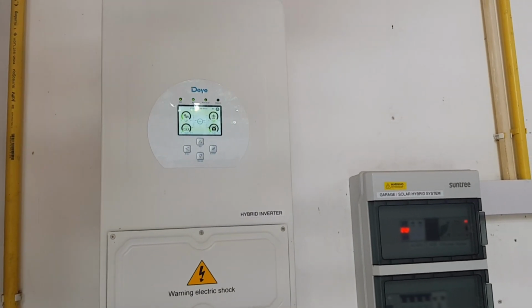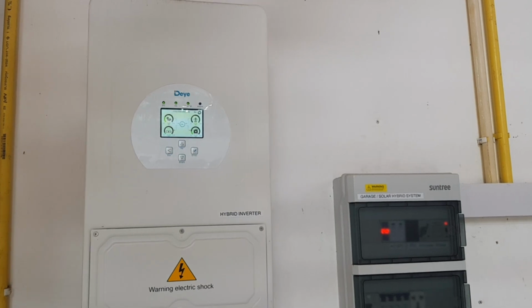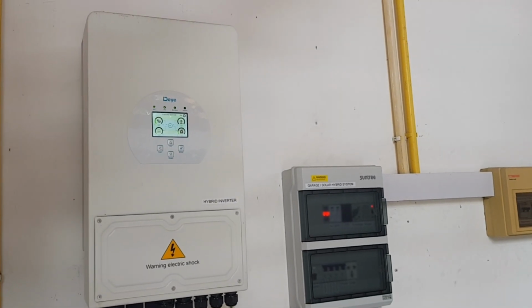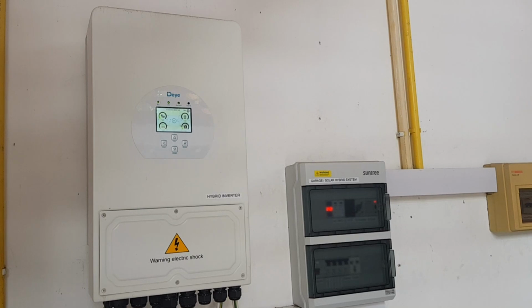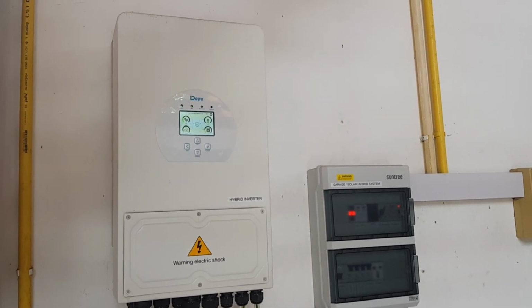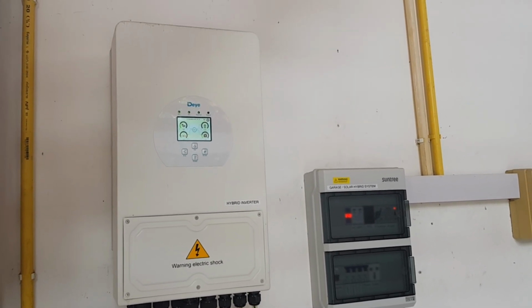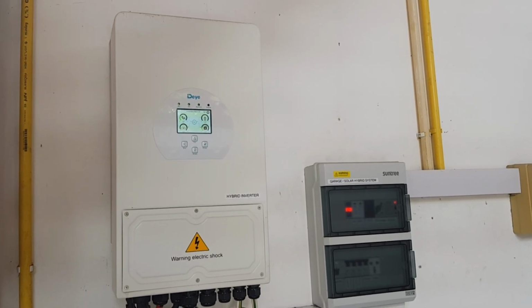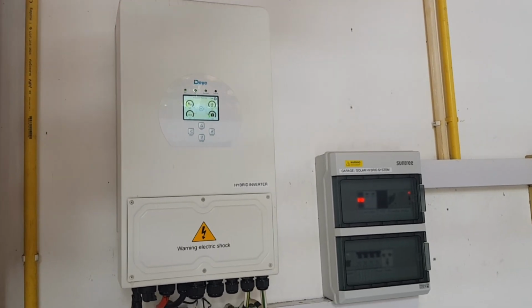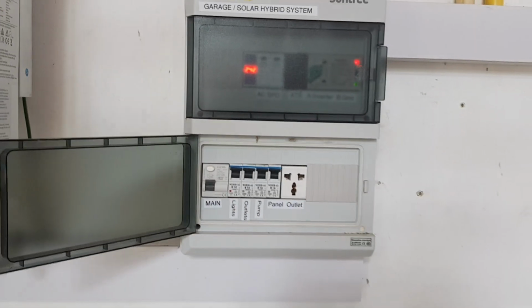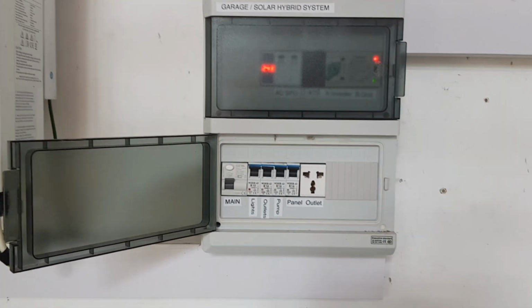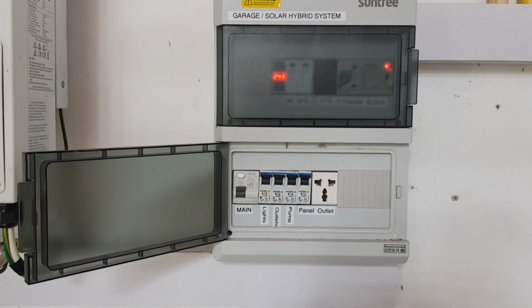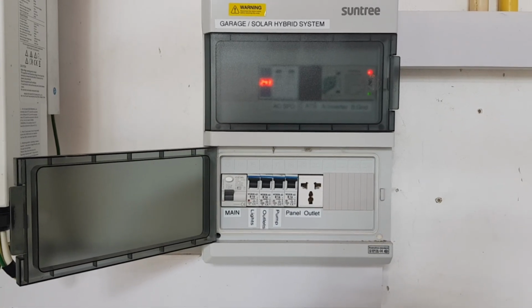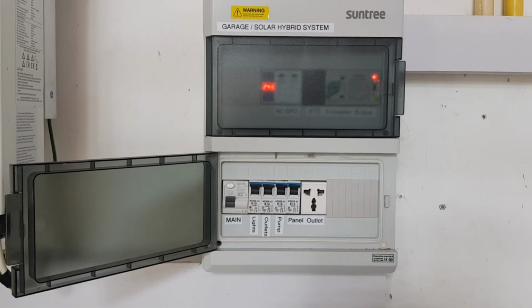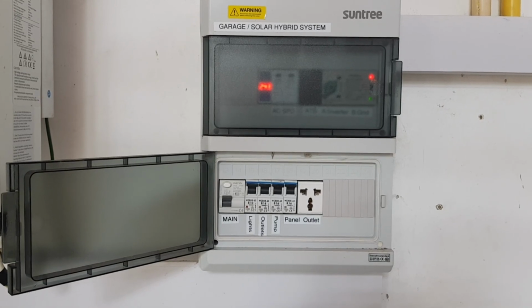This is a full hybrid inverter, and instead of having a contact which tells the state of charge of the battery, this is a contact which tells if it's off-grid or on-grid. So you can take that information directly to connect a relay which you can build into your distribution, and this would then be the output of the inverter. And if there's a relay inside there which is taking care of a neutral to ground bond, then you can also use the TT system easily.